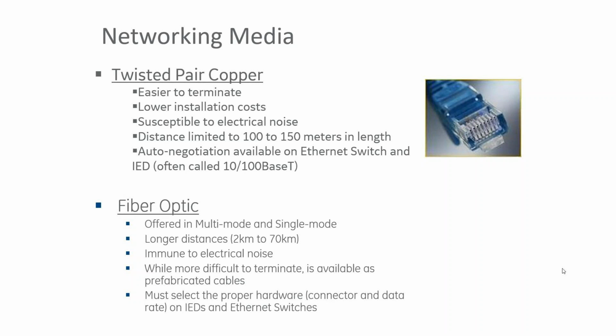The disadvantage is that it's susceptible to noise. So if you're going to use RJ45 in a substation or industrial environment, make sure to use shielded RJ45 cables, and that those shields are properly grounded. There's also a limitation on the length you can run, since it's an electrical connection and subject to voltage drop.